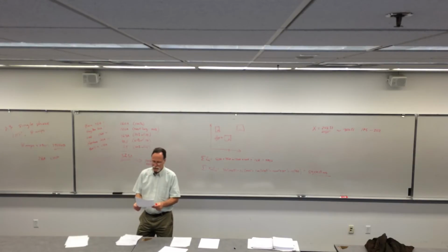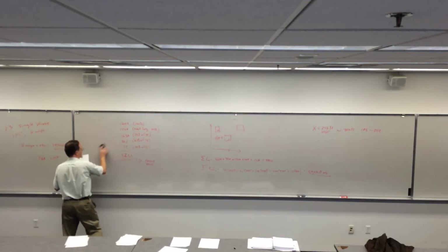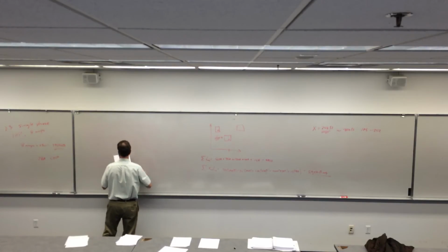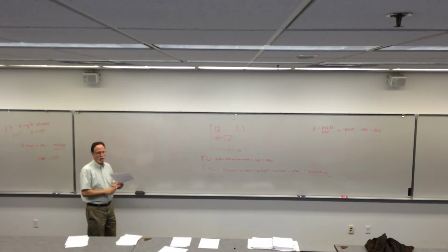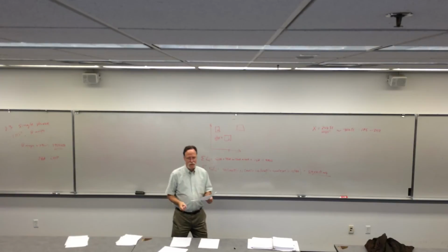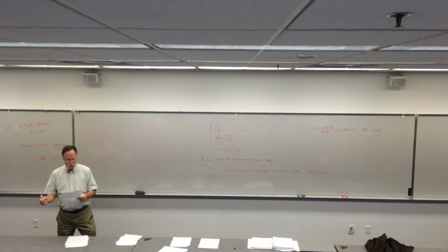So we've got that covered. Then the next thing is what size entrance would you recommend? That would be question 5. For 160 amps for the residence, what would you pick? 200 amp. How about for the feed center, which is 120 amps? 150. The second barn is 75 amps. What do you pick? 100. The hay barn is 50 amps.